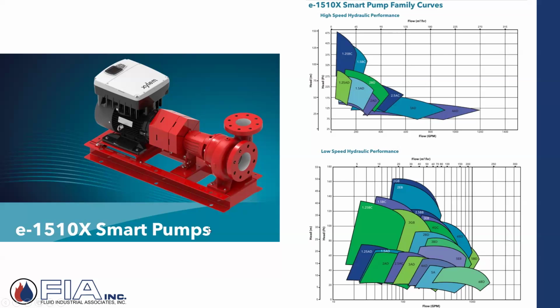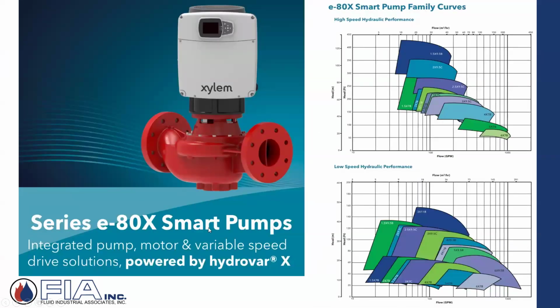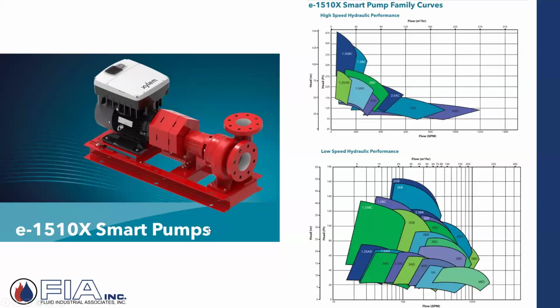I think the intent down the road would be, hey, I've got existing pumps out in the field that may be X number of years old. I can take the existing motor off and just replace it with this motor and drive technology, and put it in place with the existing end suction pump or vertical inline pump, and then have all of this super high efficient motor and variable speed capabilities right on board. So again, it's just more technology trying to improve what's available in that variable speed arena, if you will.